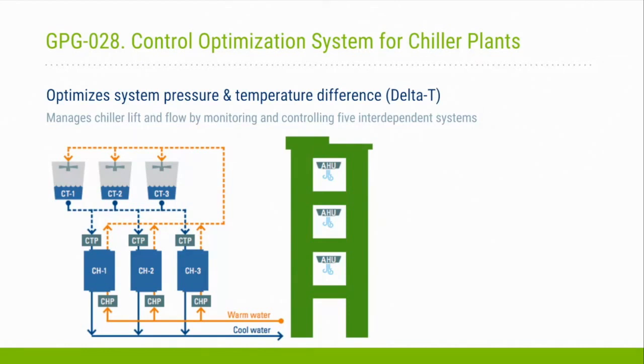Some of the things that aren't shown in this particular slide are some of the additional sensors and instrumentation that were installed by the vendor. They actually had to do some modifications. They had to add power meters for the towers. The towers had existing VFDs. The primary condenser water pumps and the primary chilled water pumps did not have VFDs, so those were added as part of the technology. In addition, there were differential pressure sensors put across each of the pumps, for the condenser water, primary chilled water, and secondary chilled water pumps, flow meters, and they actually installed quite a few temperature sensors that were higher grade, with a higher level of accuracy.